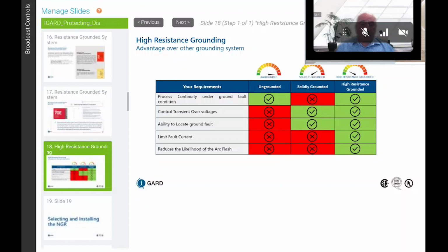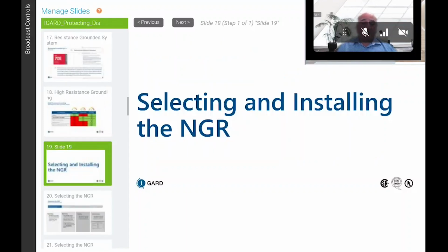With a solidly grounded system, you have control of the overvoltages, but you have to trip on the first fault. On the ability to locate the fault, I get questioned about this all the time. Some people say you just look for the smoke and you find where the fault is, but you've lost the circuit. The high resistance grounded system seems to be the one that ticks off all the boxes. You reduce the likelihood of exposure, limit the ground fault current, can locate where the ground fault is, control transient overvoltages, and have process continuity.